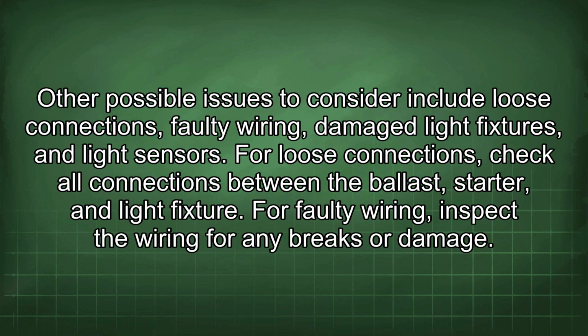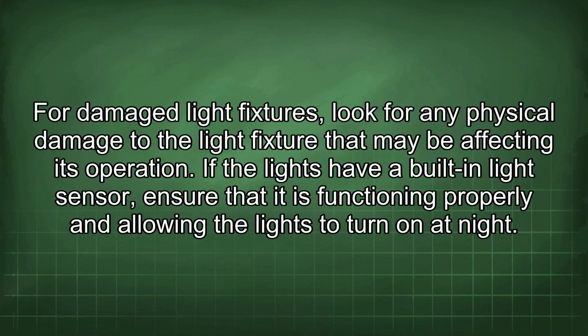Other possible issues to consider include loose connections, faulty wiring, damaged light fixtures, and light sensors. For loose connections, check all connections between the ballast, starter, and light fixture. For faulty wiring, inspect the wiring for any breaks or damage. For damaged light fixtures, look for any physical damage to the light fixture that may be affecting its operation.